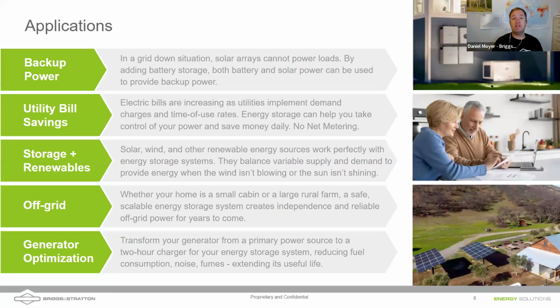Off-grid historically has always leveraged generators. Why? Because if you live in an off-grid community or an off-grid house, and I size your solar to get you through the dead of winter, the solar is going to be way oversized for summer. So a lot of times we find a balance, and we're going to integrate a generator into that system so that during a winter storm, when it's been cloudy for 4 or 5 days, we can start up that generator and recharge those batteries and then shut it off. So I've always historically seen generators in off-grid situations.